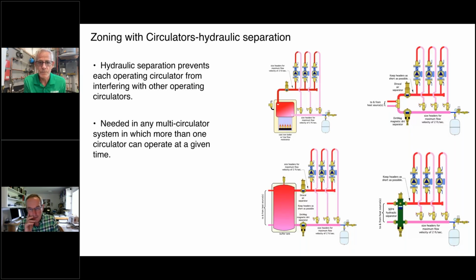Yep, the old days, I guess, for both of us, we remember when primary secondary was really popular, and you would have pairs of closely spaced T's like this along a primary loop. And to your point, as you go downstream, assuming all these loads are operating, you're getting lower and lower supply temperatures to these downstream secondary circuits.